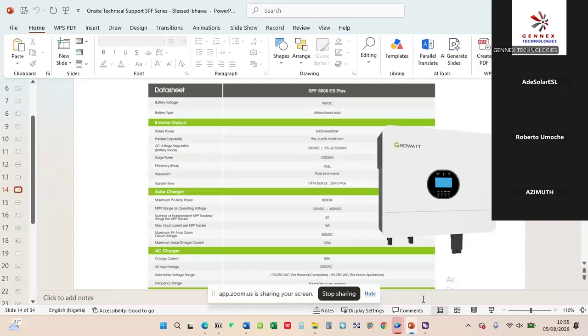For example, if all your inductive and resistive loads are working, and then someone puts on something requiring maybe twice that, it might shoot up or take more time. Some devices take longer, and their surge time is higher than what the machine can provide, so you get errors like 58 and stuff like that. Please take that into consideration.